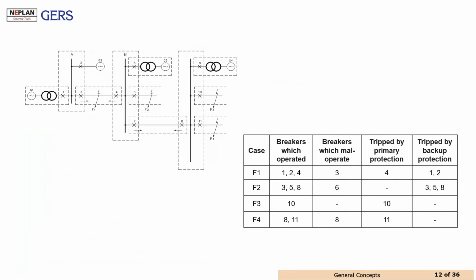To illustrate this kind of scenario, I am showing here a power system example. In this example, we have 4 generators and 4 fault locations. This slide shows, for example, fault number 1, and what would happen if the breakers that operated were number 1, 2, and 4. That means that if this fault occurs, breakers number 3 and 4 should be the primary protections. And if the breakers that tripped were 1 and 2, we can see that number 3 didn't work properly as primary protection, but number 1 and number 2 worked as backup protections.